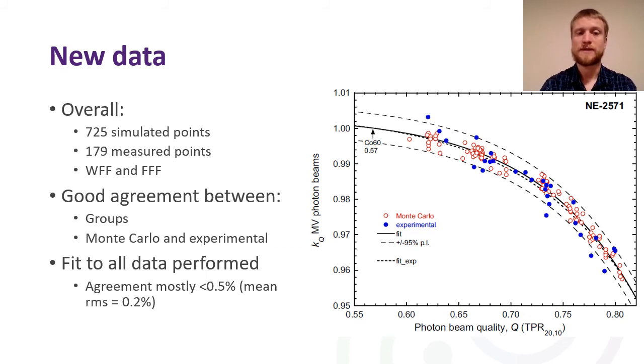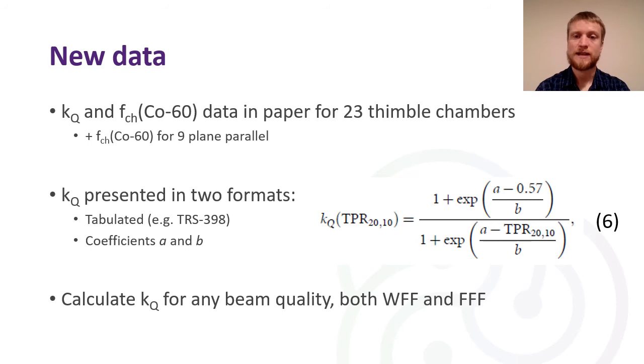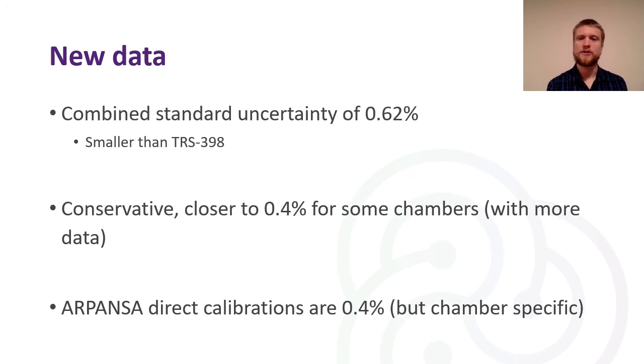For each chamber there's been a fit to all data performed. The agreement for that fit is mostly within 0.5%, and across all chambers there's a mean RMS difference of 0.2%. The paper contains KQ data and FCH Cobalt-60 data for 23 different Thimble chambers, as well as FCH Cobalt-60 for nine different plane-parallel chambers. The KQ in the paper is presented in two formats: a tabulated format as familiar from TRS-398, as well as function fits with coefficients a and b, giving KQ as a function of TPR20,10. This consensus data set shows a combined standard uncertainty of 0.62% in KQ, smaller than seen in the TRS-398 protocol.